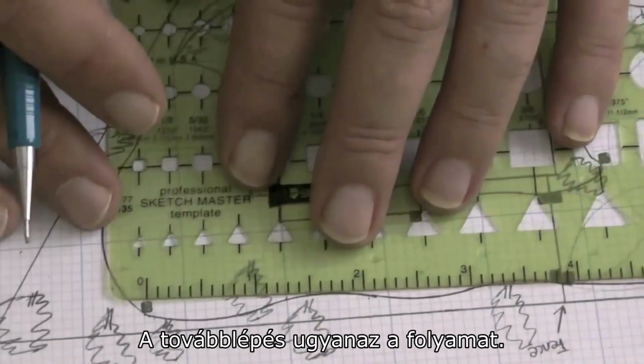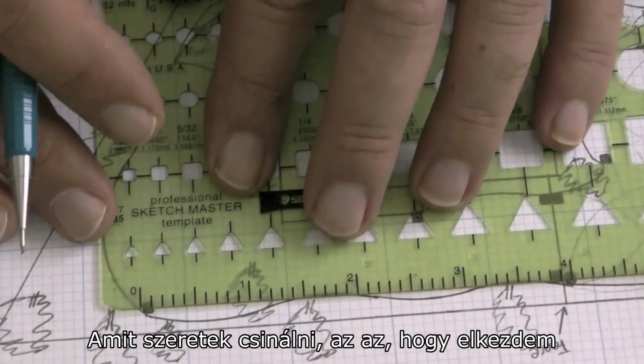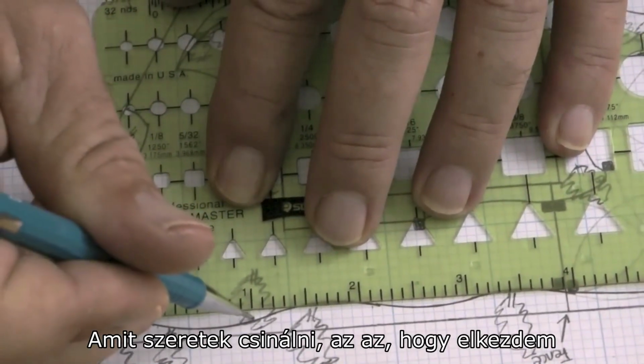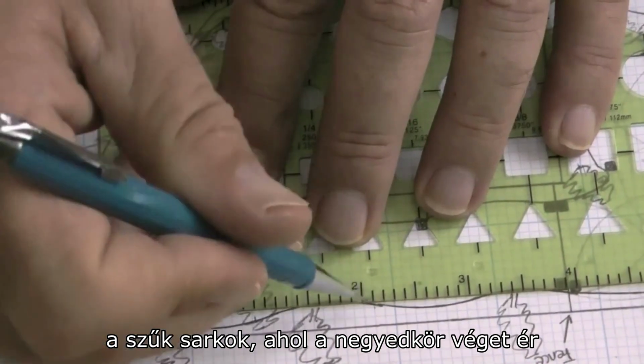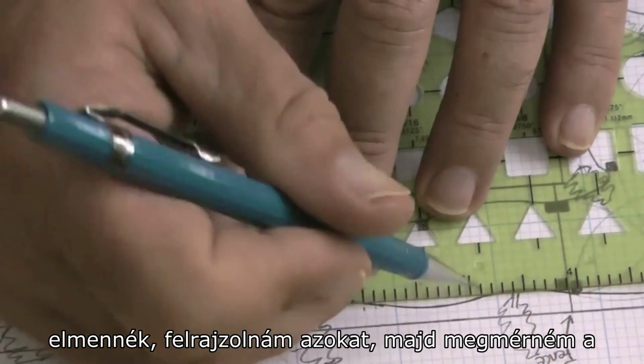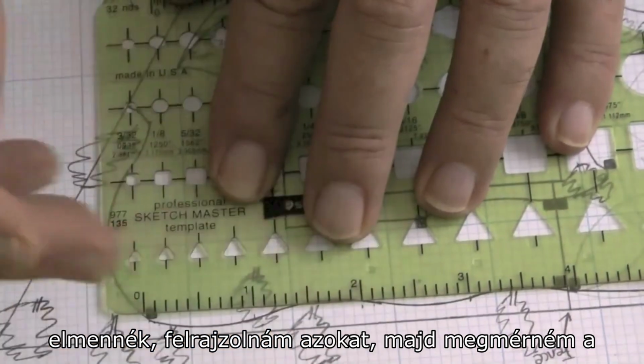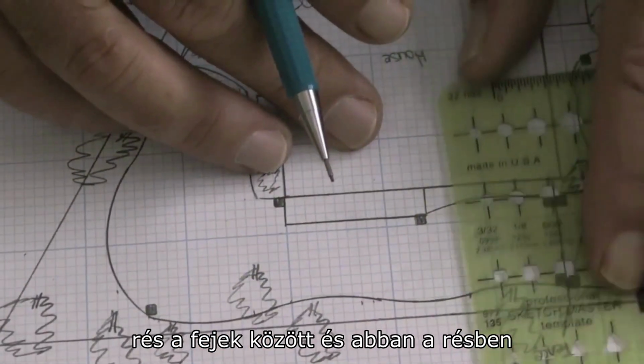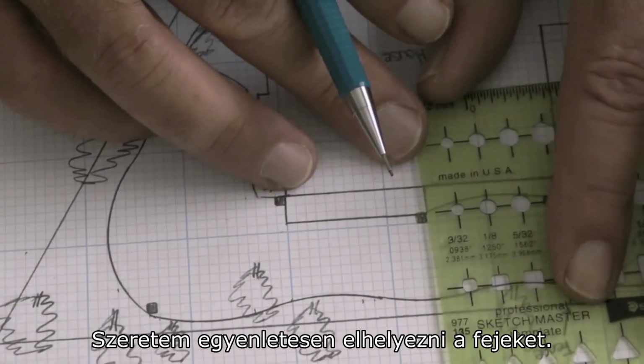Moving on, it's the same process. What I like to do is start in the tight corners where the quarter circle heads would go, get those plotted, then measure the gap between those heads, and in that gap I like to evenly space heads.